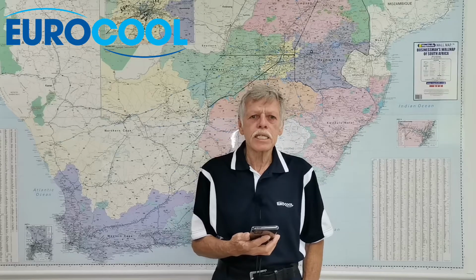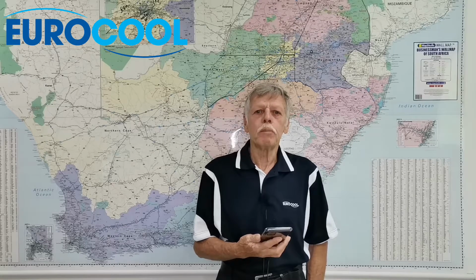So E6 is not that daunting. It's just basically rechecking your forward and backward communication. In the case where your outdoor also runs on a printed circuit board, there could be a fault where the unit is trying to talk to the outdoor but getting no response back. Almost like when you ask your wife to make you a cup of coffee. The response is slow. So check that you are getting power at the outdoor board.